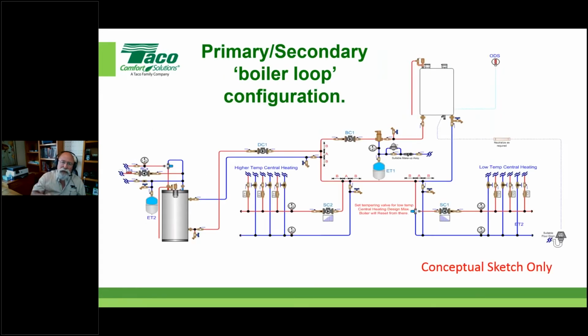Let me ask a question. Give me some quick feedback. Anybody pipe like this anymore when we're talking about condensing equipment, okay? And I'll call this a boiler loop. That's where you come out of the boiler, you make a nice big halo or a big loop, and then off of that you do your closely spaced tees, and you take care of your highest temperature first, next highest temperature next, etc. Anybody out there still piping this way? It's kind of a throwback to the early days of getting multiple temperatures on a traditional cast iron atmospheric boiler, but some people have taken that concept and kept it with condensing equipment.